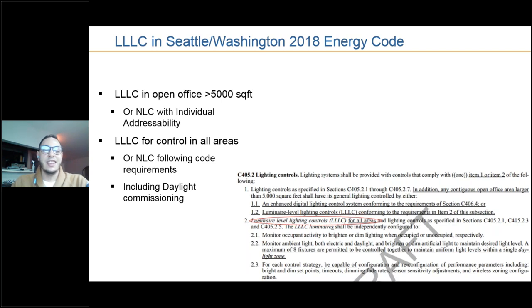And for your space, as it's written in the code, you would want to have luminaire level controls for all the areas, or implement network lighting controls following all the code requirements, including daylight commissioning, where you need your primary daylight row and your secondary daylight row. These all need to be wired and responding to different sensors, which can be very laborious and inefficient. With luminaire level lighting control, each fixture has a daylight sensor, so you don't necessarily need to worry about this primary, secondary daylight zone wiring. It's all done and commissioned through a phone app.